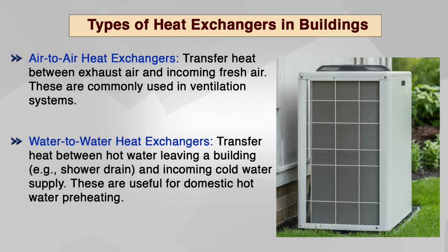Second is water to water heat exchangers. As the name suggests, these exchangers transfer heat between hot and cold water streams. For example, they can recover heat from wastewater leaving showers or sinks, and preheat the incoming cold water supply for showers or laundry. This reduces the energy needed to heat the incoming cold water to the desired temperature.